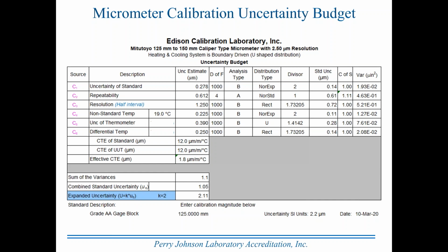Now, I'd like to say, just as a side light to this, that typically when you're calibrating micrometers, a laboratory will state on their scope the capability of calibrating, from very small to very large. Now, calibration can only be performed when you have a calibrated standard to compare to. Calibration isn't the adjustment of a micrometer or an instrument to make it in spec. Calibration is simply the comparison of that device to a device of known value. In this case, the comparison of a micrometer with unknown performance against a gauge block of known performance with known uncertainty. So because it requires a standard, you can't calibrate 0. You can verify that a micrometer will close down to 0 with nothing between the anvils. But by definition, if it's nothing within the anvils, there can't be a standard.